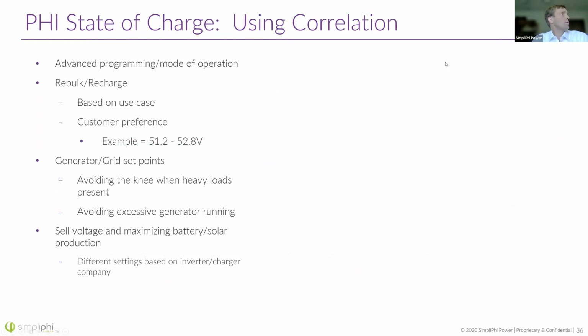Most charge controllers have advanced programming for charging and discharging. The settings we're putting in here tell the inverter when to stop discharging the battery, stop selling energy to the grid, and start charging the battery up again. That's the re-bulk recharge setting in the inverter.